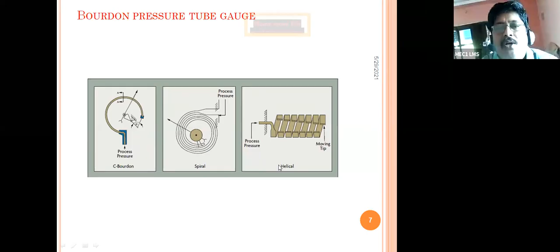See here, process pressure. We have to apply process pressure here, and thereby the Bourdon tube expands. If the pressure is less, it contracts. If the pressure is more, it expands. Thereby, with some arrangement, the pointer deflects on the scale. That means in the Bourdon tube, we have C Bourdon tube, spiral Bourdon tube, and helical Bourdon tube.